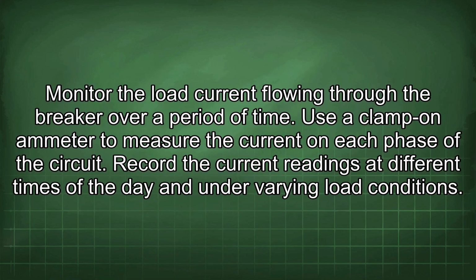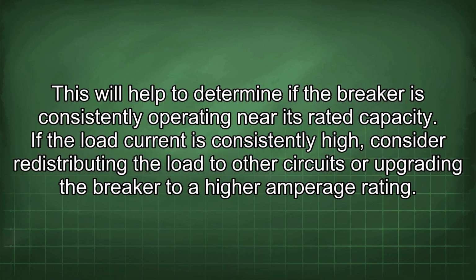Monitor the load current flowing through the breaker over a period of time. Use a clamp-on ammeter to measure the current on each phase of the circuit. Record the current readings at different times of the day and under varying load conditions. This will help to determine if the breaker is consistently operating near its rated capacity.